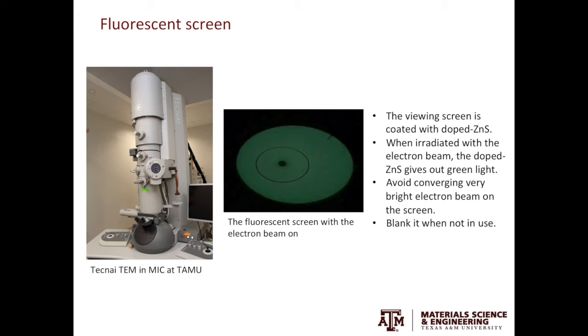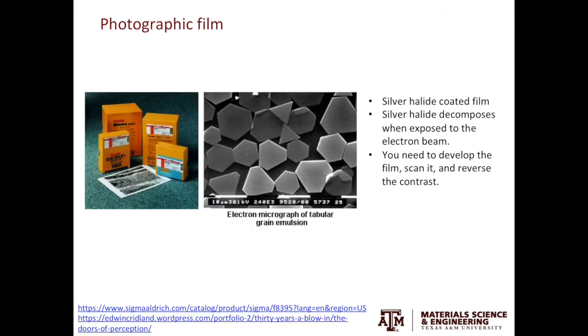The screen is pretty robust, but we still need to be careful with a couple of things. First, try not to converge a very bright beam and leave the beam on a specific spot on the screen for very long — if you do that, you may burn the screen, and you can see a burned mark at the center of the screen here. Second, cover the screen when not in use, especially when you turn on the light, as photons from the light may degrade the screen over time.